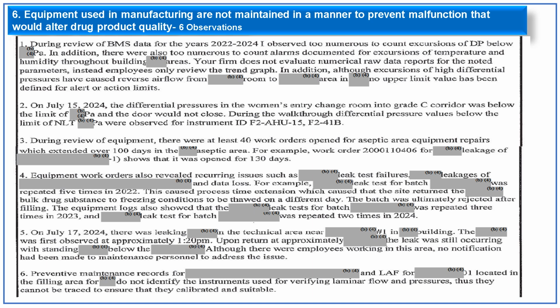The first one: during review of the BMS data from 22 to 24, numerous excursions were observed in the temperature as well as the differential pressure. The firm did not evaluate the numerical raw data reports for the noted parameters. Instead, they only reviewed the trend graph. Although excursions of high differential pressure have caused reverse airflow from a specific area, no upper limit value has been defined for the alert or the action limits.